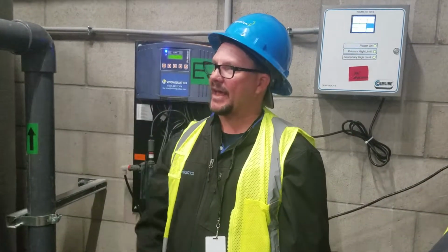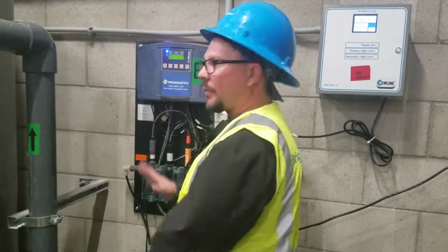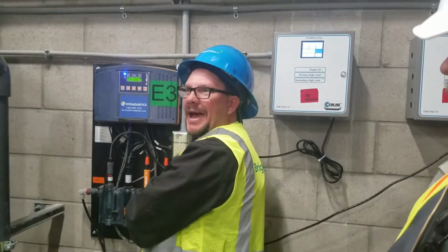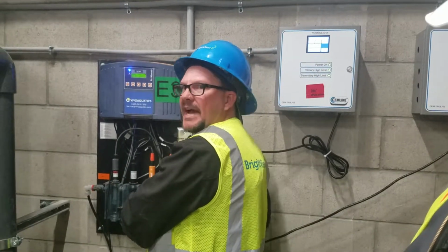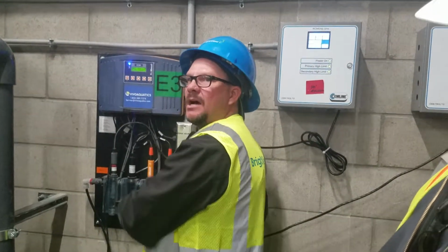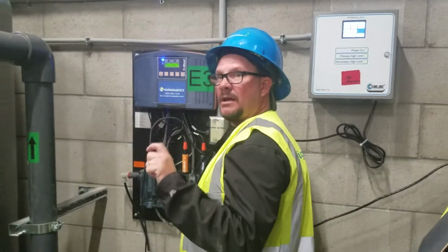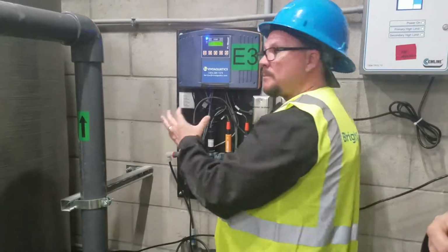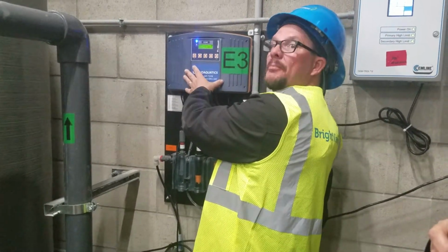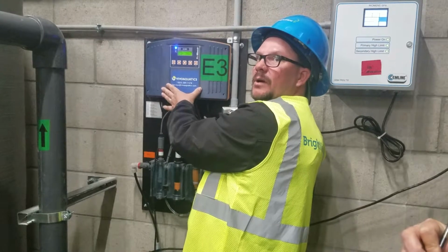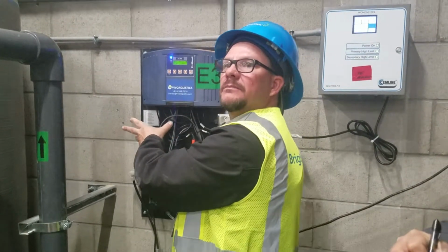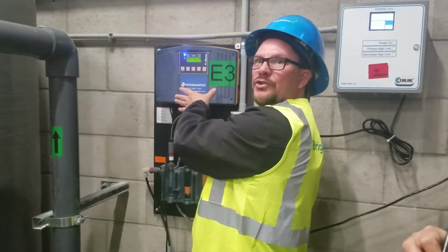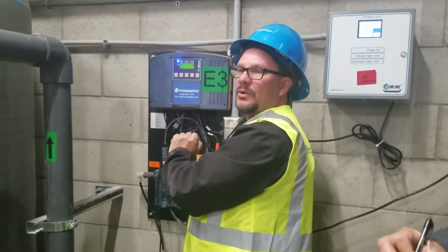Just doing a lot of hand testing. When these probes are working properly and these numbers are corresponding with them, we call that tracking. So the terminology is: is your probe tracking properly based on what you're getting for your physical reading? And I think you guys use Taylor test kits, which is ideal, because that's all we like to use when we come up here to program and calibrate. We won't calibrate based on an Allen test kit. There's too many variables involved in that. It's a great kit, but we just don't use it to calibrate with. So use your Taylor test kit.